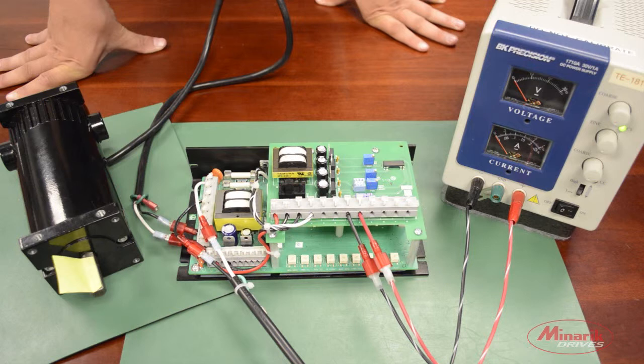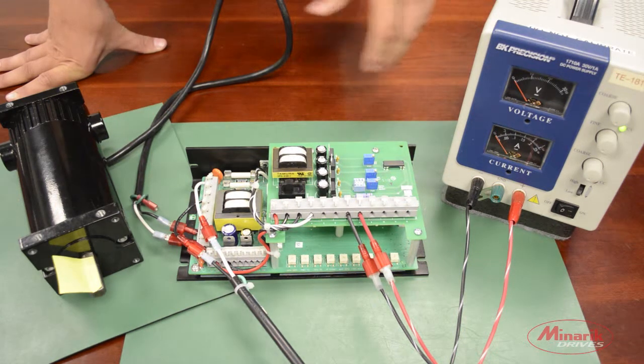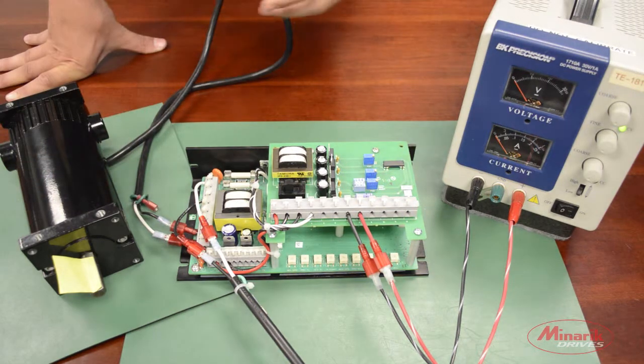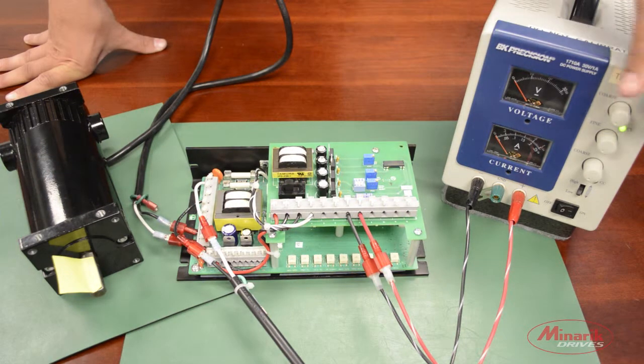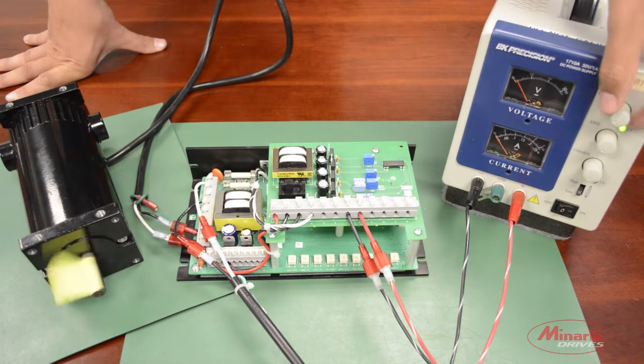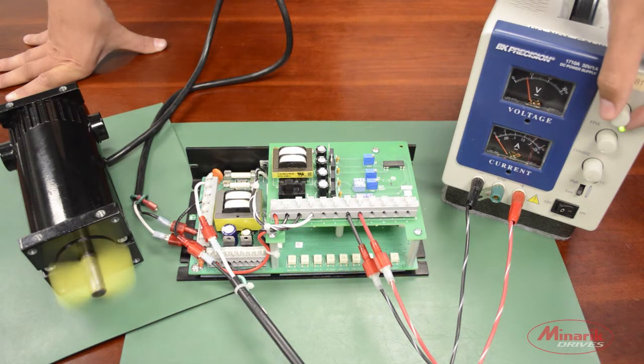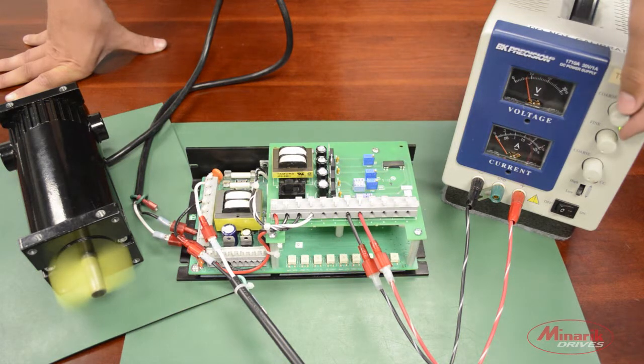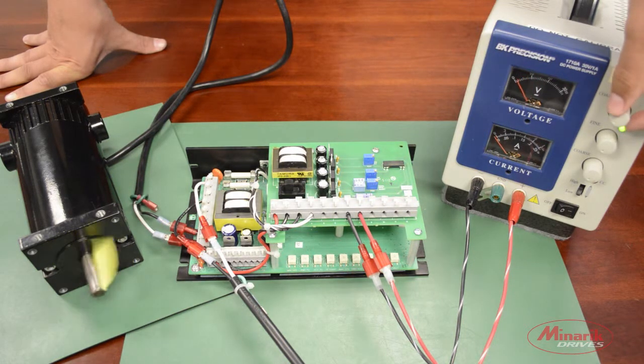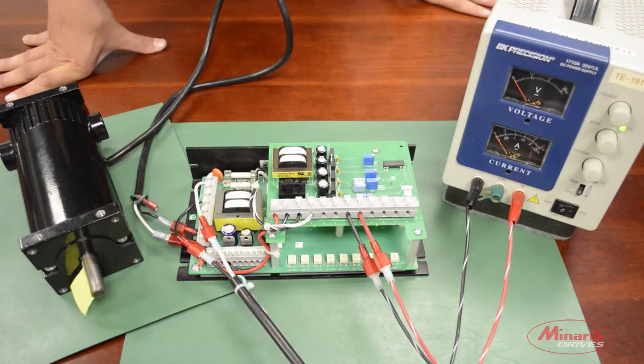Now that we've finished calibrating the isolation card, we're going to go over a quick test procedure to confirm that we're getting the correct speed out of the motor we require for our application. So we'll cover the full input voltage range starting at 0 volts. We'll slowly increase our input voltage range to 10 volts. And then we'll reduce it back down to 0. And everything seems to be working properly.